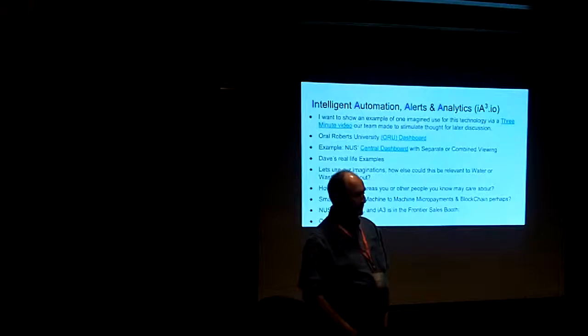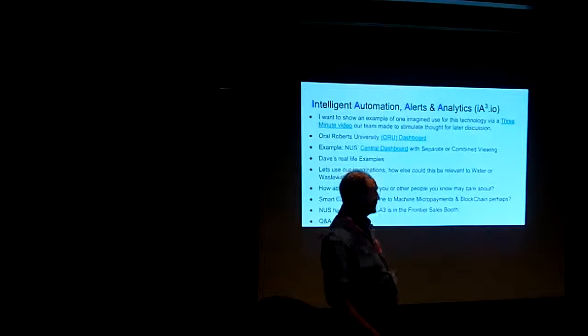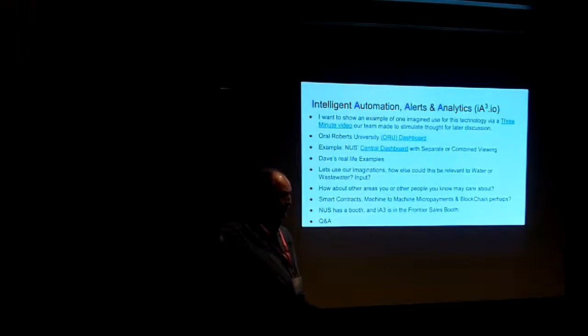About a year or two ago, we installed a chlorine sensor there because they were always chasing the chlorine, and then the guy who had been watching it wasn't available anymore. So we installed this system to monitor it remotely. With the combination of the point analyzer and then the flow meter we added, we were able to get basically the data you see there. Between the analyzer and the flow meter, about $3,500 to $4,000, and the actual install, I think we've got on the books $7,000 total. So for the install, and then the subscription for this site, I think it's $200 to $250, something like that, if I remember correctly.